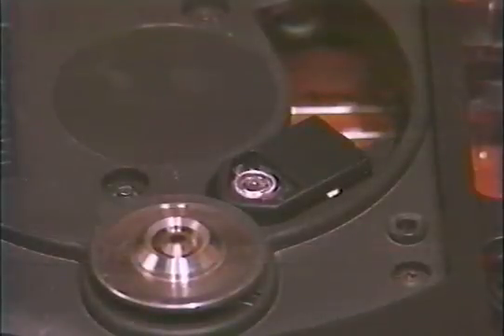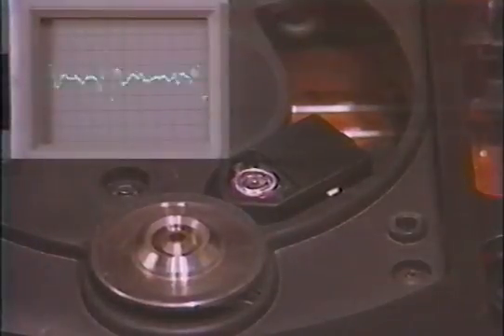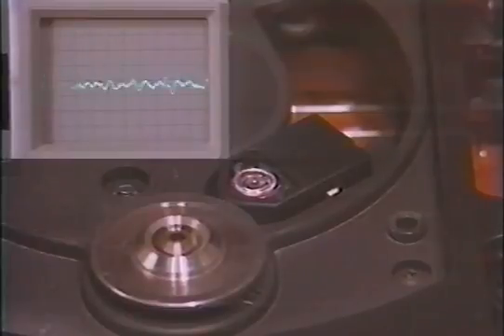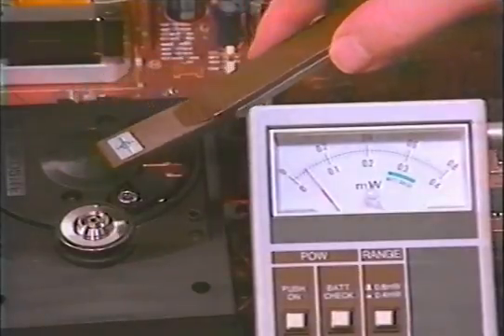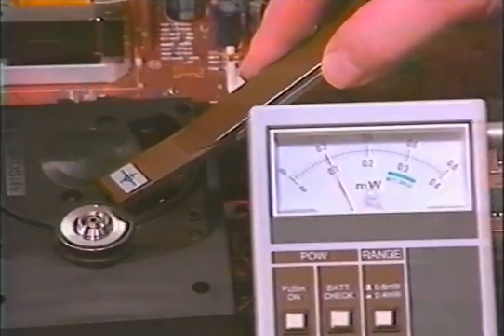When the focus test mode is implemented, the optical pickup's laser diode turns on, and the objective lens continuously moves up and down. This test mode allows the focus servo to be tested without the other servo circuits. This mode allows troubleshooting of the laser control and focus startup with and without a disc. The focus signal can be monitored when troubleshooting the focus servo circuit. Here we see the focus drive signal under normal operating parameters. The laser output can also be checked while in this test mode.